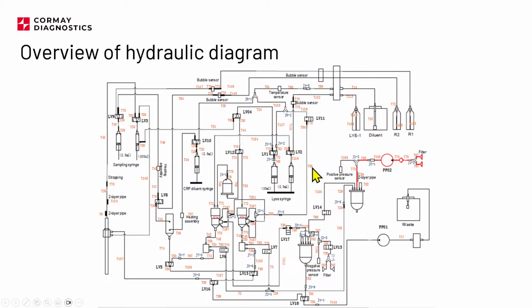What else are we seeing? There is like a strange thing here, right? We're supplying diluent by this valve, and there is like a three-way connection going from the outside, and then we are going to the second, and then we are going back, and we are going to the negative pressure chamber. And actually, this is part of the impedance channel and also part of the rinsing circuit for the aperture. When you want to make a measurement, you simply need to open this valve, and when we have negative pressure here, the liquid from here and also from this port will be drawn into this negative pressure chamber, right?